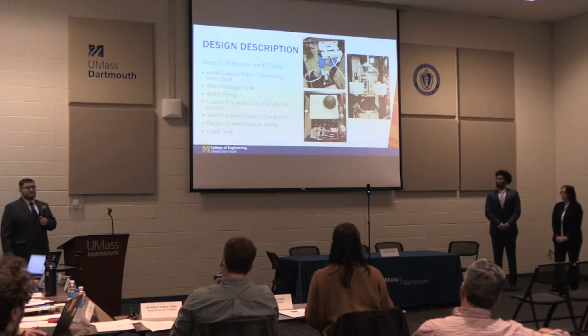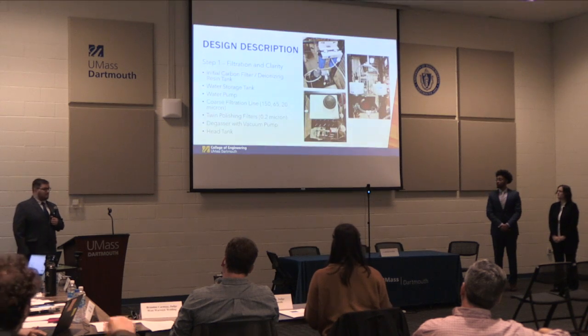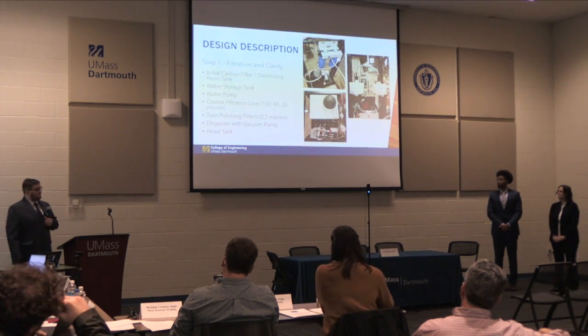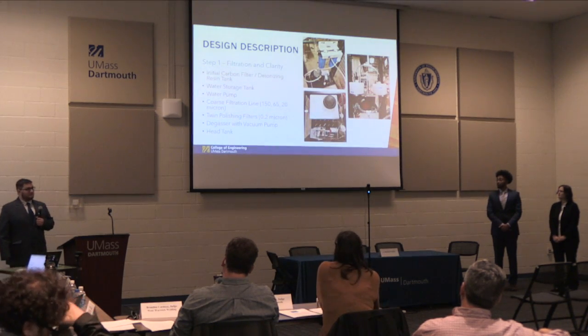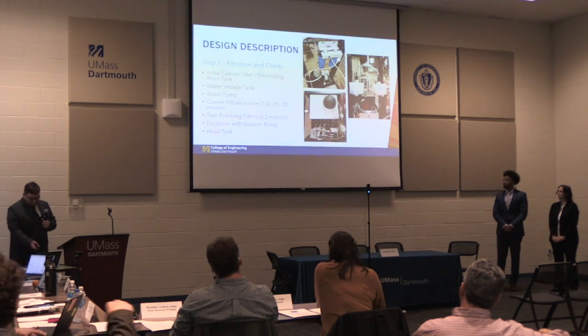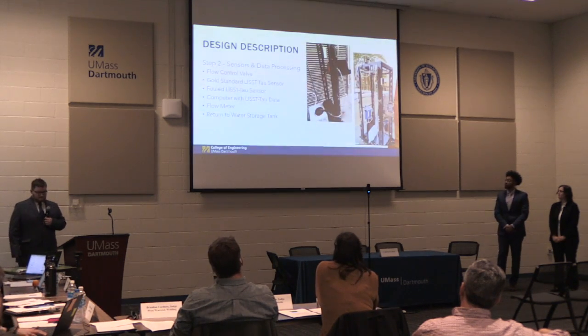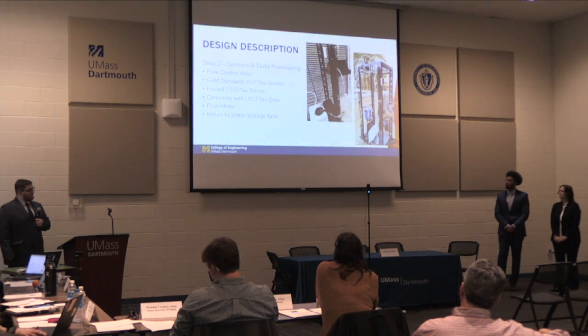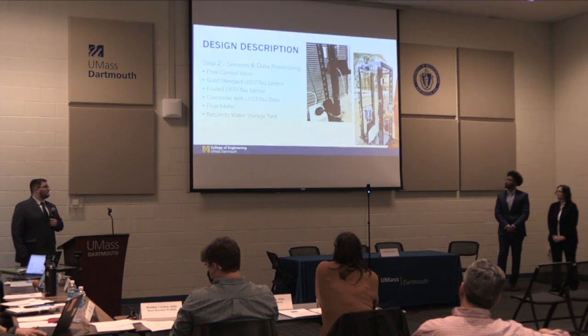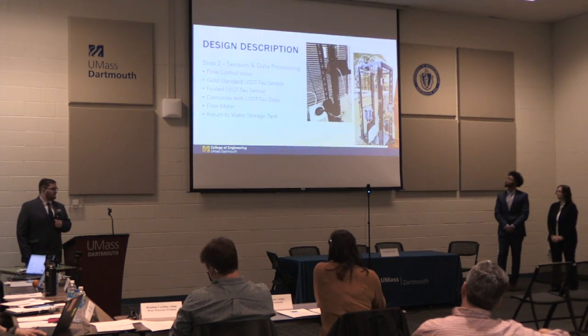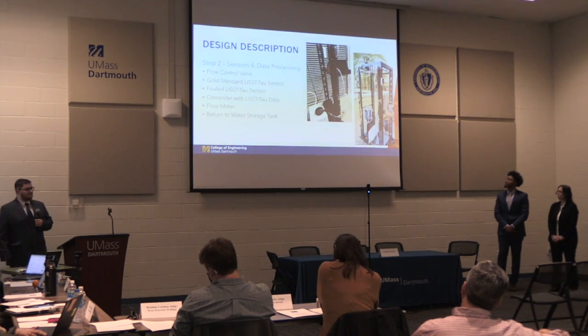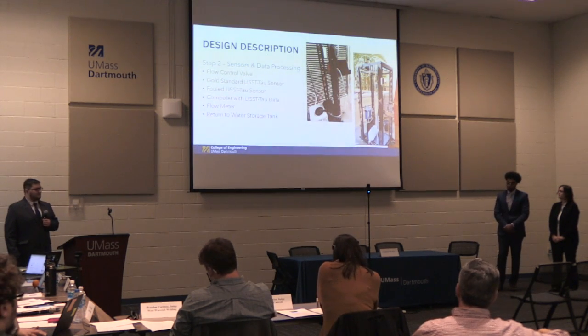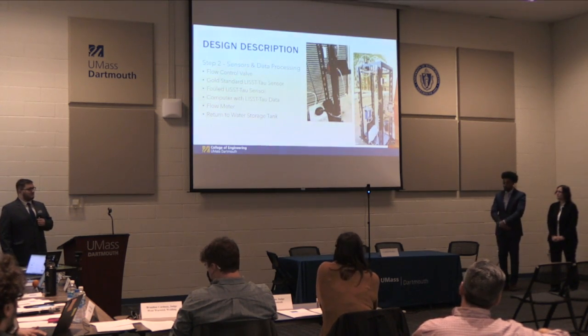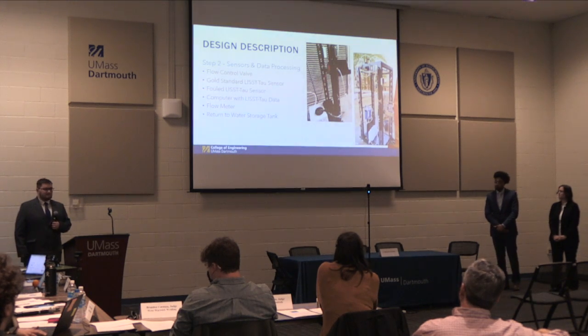And then out of the filters, we go through the degasser to remove any of those air bubbles, and then into our head tank. From our head tank, we then start to utilize the gravity flow to pass the sensors. So we can use our flow control valve right out of the head tank to set our desired flow rate. And then the water will pass through our gold standard LISST-Tau sensor to get those baseline readings.